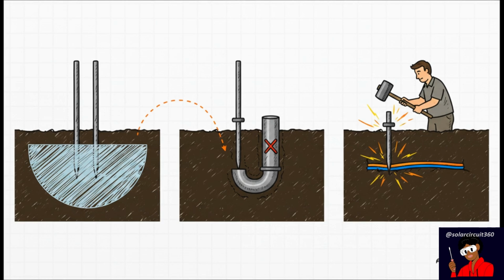You also have to watch out for buried metal, things like rebar or water pipes, which can hijack the current and give you a fake reading. And it goes without saying, never blindly drive metal stakes into the ground without checking for underground utilities first.